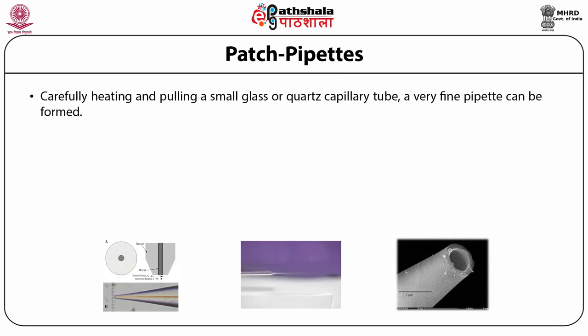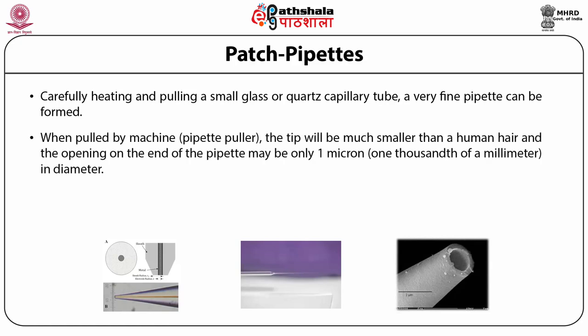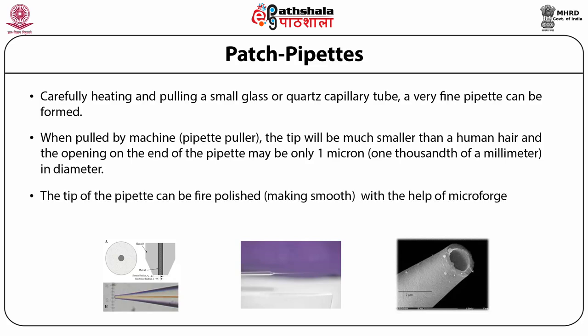Patch pipettes are the most important part of any recording. They can be made by carefully heating and pulling a small glass or quartz capillary tube to form a very fine pipette tip. When pulled by a pipette puller, the tip will be much smaller than a human hair and the opening on the end of the pipette may be only one micron in diameter. The tip of the pipette can be fire polished — meaning made smooth with the help of a microforge.